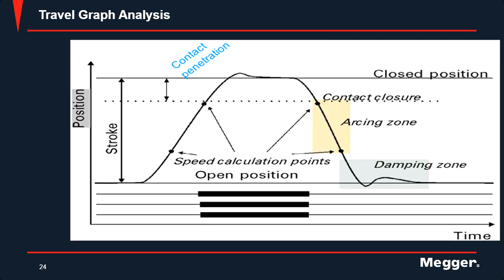So we have our travel curve here. I'm just going to go through a few little points on it to show you what you're looking at on that trace. The first thing you have is your stroke. That's the total distance your operating mechanism traveled. Then you have your penetration, which is your contact penetration. This is the length measured from the initial contact touching to the final resting position of the operation. This is referring to an interrupter with a main contact and an arcing contact. I'm going to go through the characteristics of that in a little bit and show you exactly what those are. Then you have your overtravel, which is measured directly from the travel curve, and it's the maximum displacement beyond the resting point of the contacts during its operation.